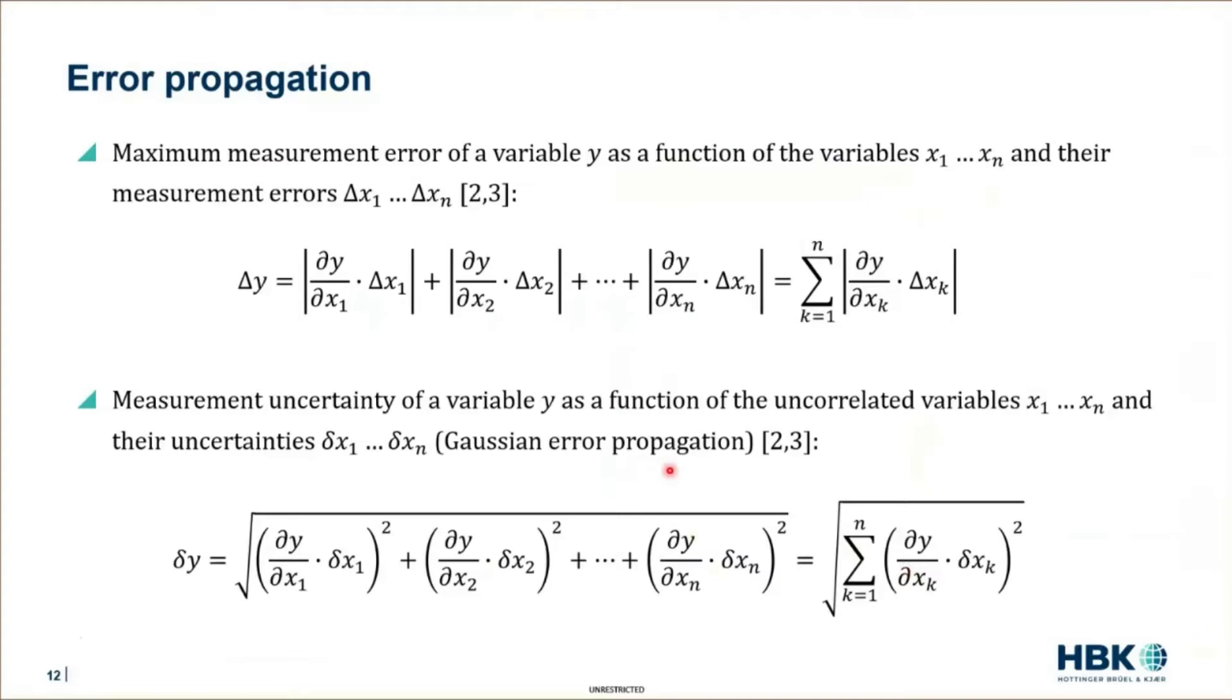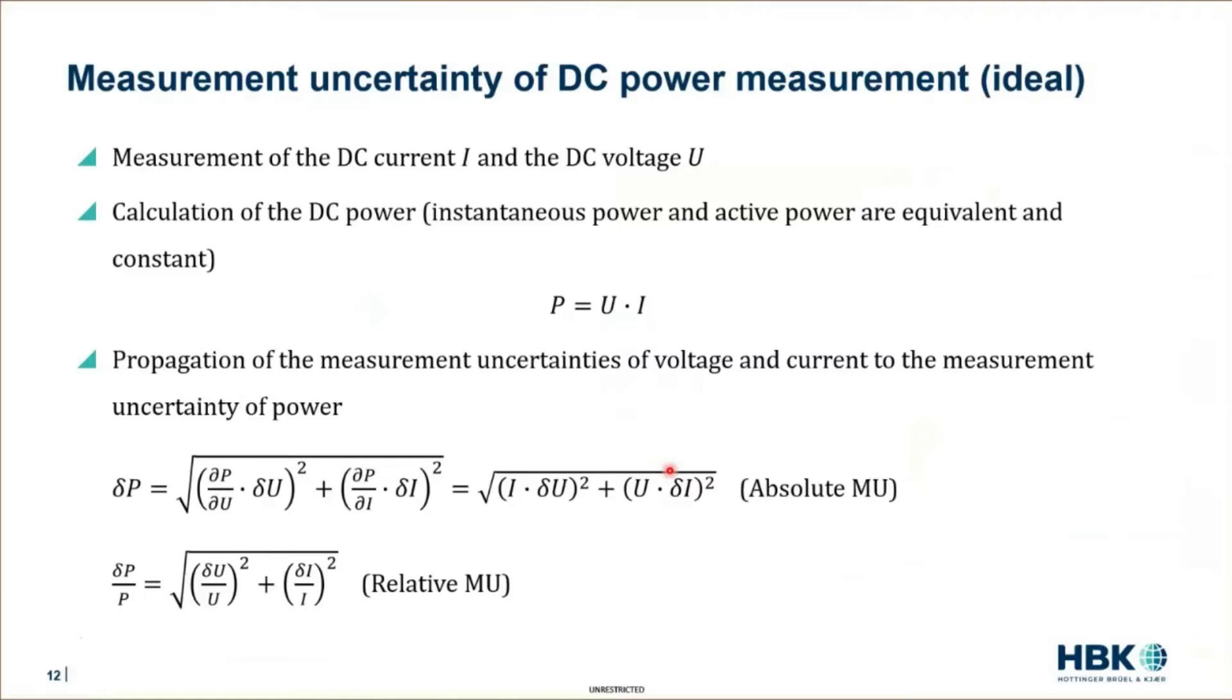We can now use these formulas to apply that on the active power. In this easy example, the DC active power, which is well known as the product of the DC voltage and the DC current. If you apply the Gaussian error propagation, then you will see that the relative measurement uncertainty of active power is equal to the squared sum of the relative measurement uncertainty of the voltage and the relative measurement uncertainty of the current.